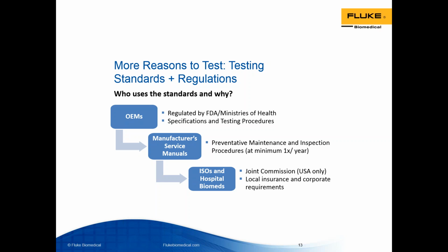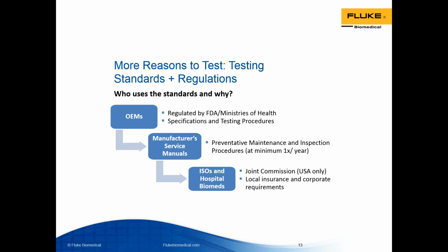And who uses the manufacturer's service manuals? Well, independent service organizations and biomeds and hospitals. Local insurance and corporate requirements will also frequently conform and then require compliance with the standards. The Joint Commission, which is in the USA only, audits and accredits hospitals, including the biomed departments. The medical device testing accreditation is based on the hospital's medical device management plan, and testing is to be based on the manufacturer's recommendations unless other independent objective evidence shows alternative testing is effective. So all of these then circulate back to the standards, and why testing incubators to the standards is important.